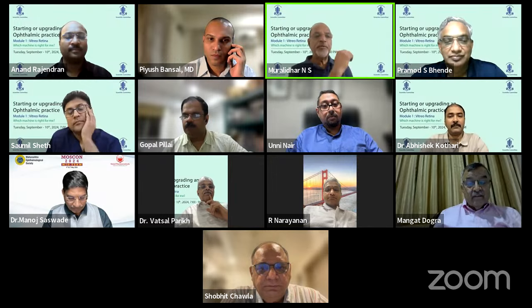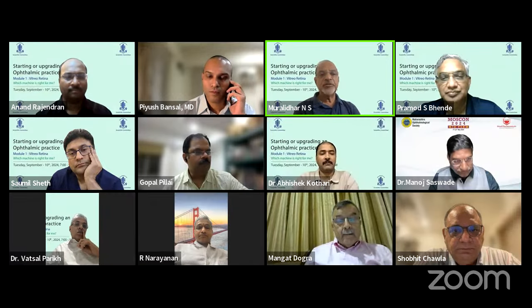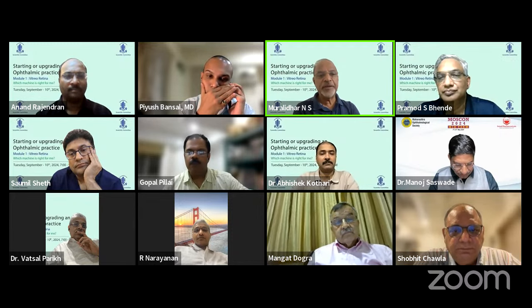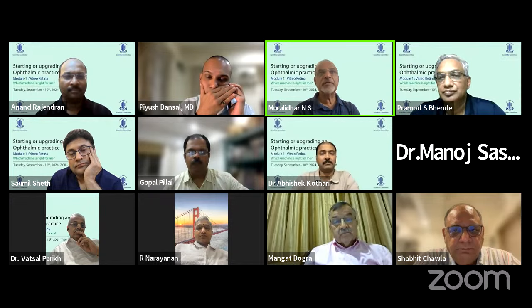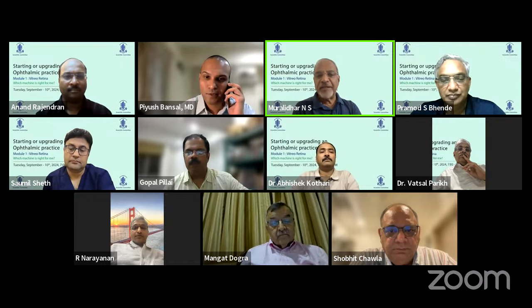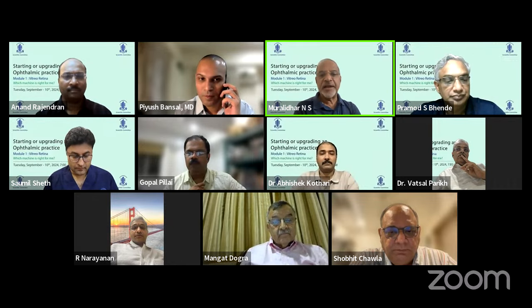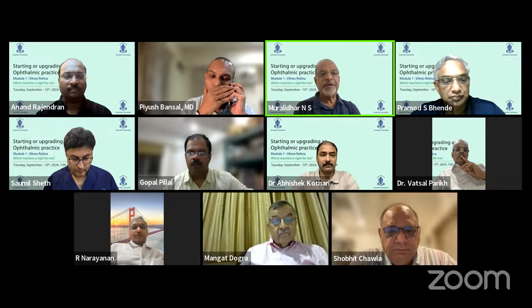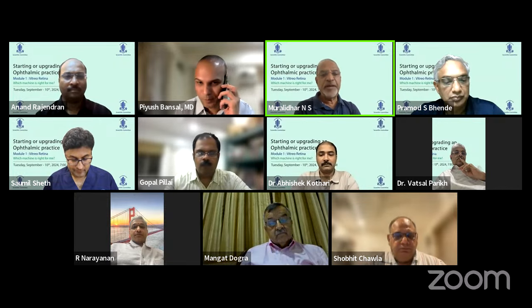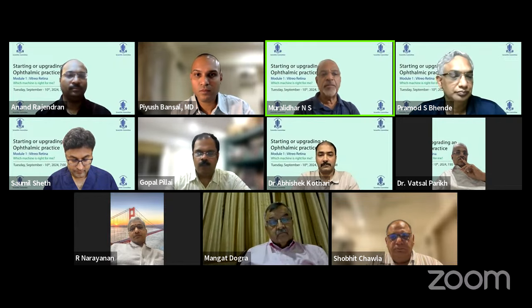Remidio is coming out with more innovations, and they do have the capability to do a little bit more wide field. So I think in future, we are going to have a lot more cheaper versions of Indian-made cameras available. And for somebody who wants a workhorse fundus camera to document retinal pathology, not really wide field, like macular pathology, as Raja was telling, for your routine diabetic retinopathy, vein occlusions, CSR and AMD, any of these Indian-made cameras like the Remidio or the Trinetra with FA capability do quite well, and they're a good investment, and really not high on your pocket.